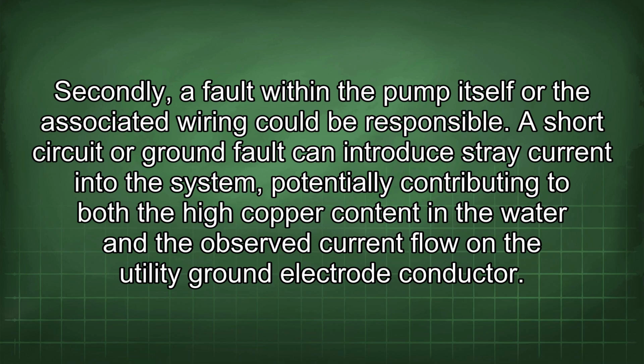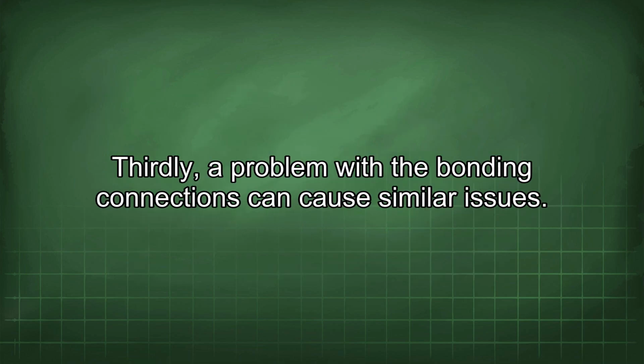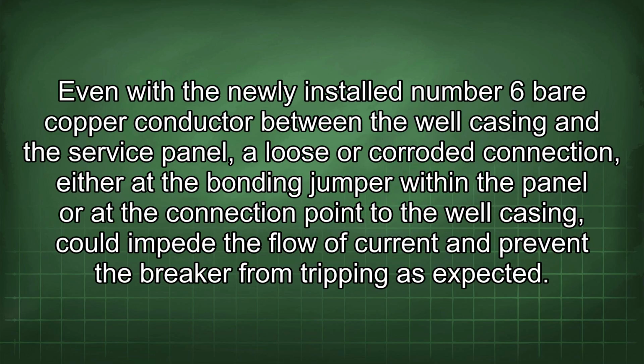Secondly, a fault within the pump itself or the associated wiring could be responsible. A short circuit or ground fault can introduce stray current into the system, potentially contributing to both the high copper content in the water and the observed current flow on the utility ground electrode conductor. Thirdly, a problem with the bonding connections can cause similar issues. Even with the newly installed number 6 bare copper conductor between the well casing and the service panel, a loose or corroded connection, either at the bonding jumper within the panel or at the connection point to the well casing, could impede the flow of current and prevent the breaker from tripping as expected.